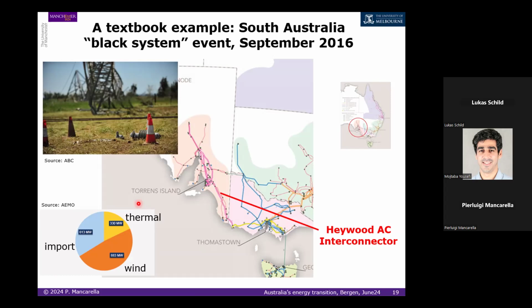So what happens is that at some point, much of this wind tripped off because of the protection mechanisms of the wind turbines, which were not properly set to deal with the different dynamic phenomena coming from the lightning strikes. So wind tripped off, and South Australia lost lots of generation.